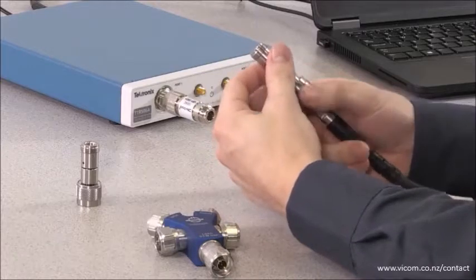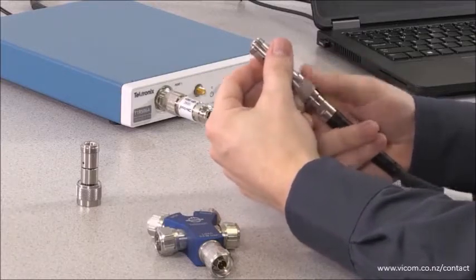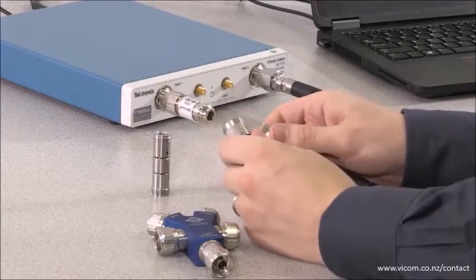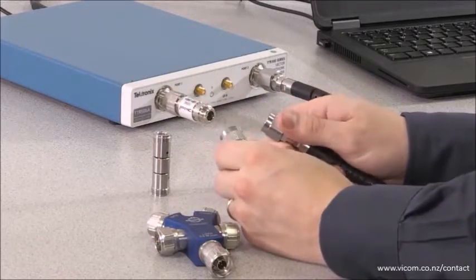But due to the electrical difference between the female-to-female adapter and the male-to-female adapter, we're gonna have to take another calibration step called port extensions.